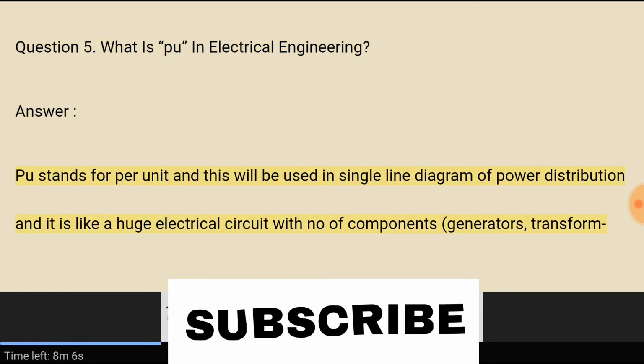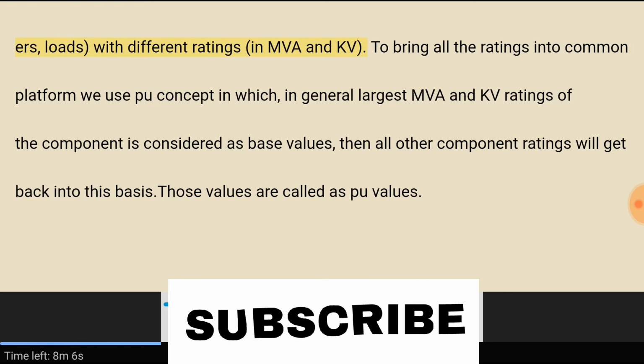Answer. PU stands for per unit, and this is used in the single line diagram of power distribution, which is like a huge electrical circuit with a number of components, generators, transformers, loads, with different ratings in MVA and kV. To bring all the ratings onto a common platform we use the PU concept, in which, in general, the largest MVA and kV ratings of the components are considered as base values, and then all other component ratings are converted to this basis. Those values are called PU values.